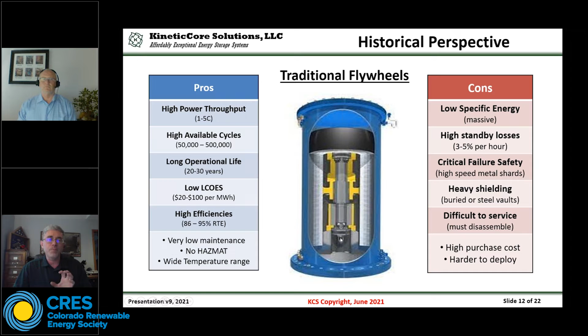The other big advantage of this design is that we're able to shift all of our power systems to outside the vacuum enclosure, which makes maintenance extremely simplified and allows ease of cooling of the electronics. Whereas with the standard design, all the electronics for the motor generator are buried deep inside the flywheel structure itself. Being able to pull them out and access them makes maintenance and operations much easier to apply.